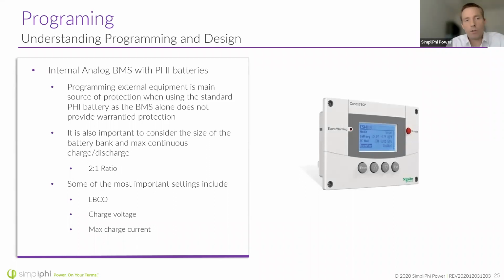Some of the most important settings, of course, are not done with the battery management system, but are done on the equipment outside. So it's very important, even though these systems have battery management systems, that the equipment operating with Phi batteries with analog BMS units be programmed properly. That means setting the low battery cutout voltage properly for our batteries at 48 volts if you're doing 100% depth of discharge. It's also very important to set the charging cycle voltages right, and we have integration guides and other documentation explaining how to do this.